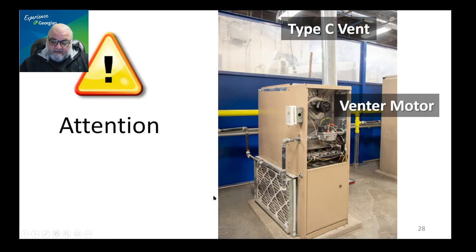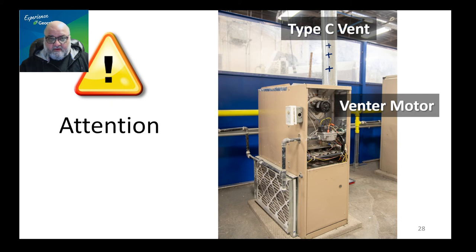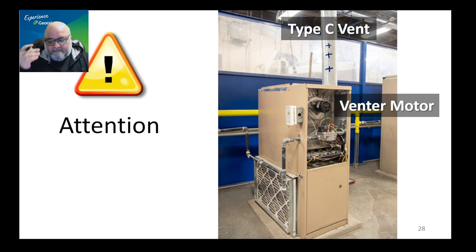Sometimes you're going to see a venter motor attached to a type C vent. The biggest issue with this is that the motor creates positive pressure in the pipe, and type C vent is not airtight or gastight at all. If there is a crack, opening, or seam, the flue gases will be pushed out because of the positive pressure inside. You can easily leak great amounts of flue gases if you do that.